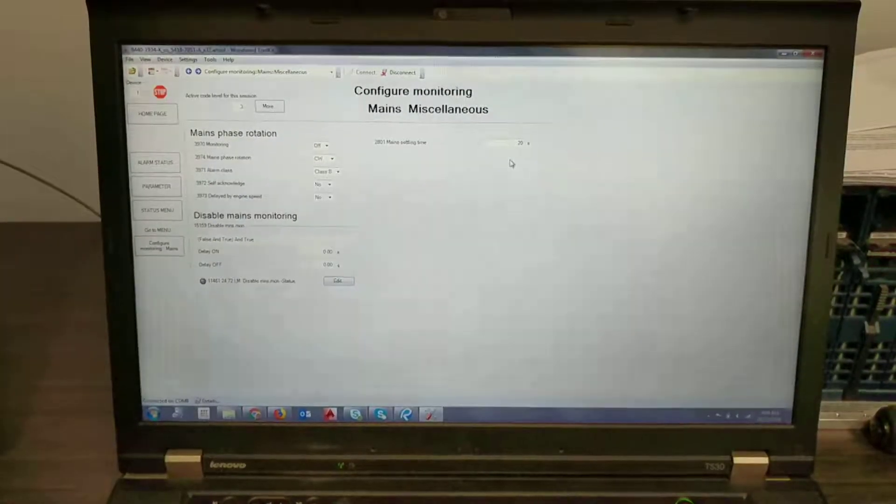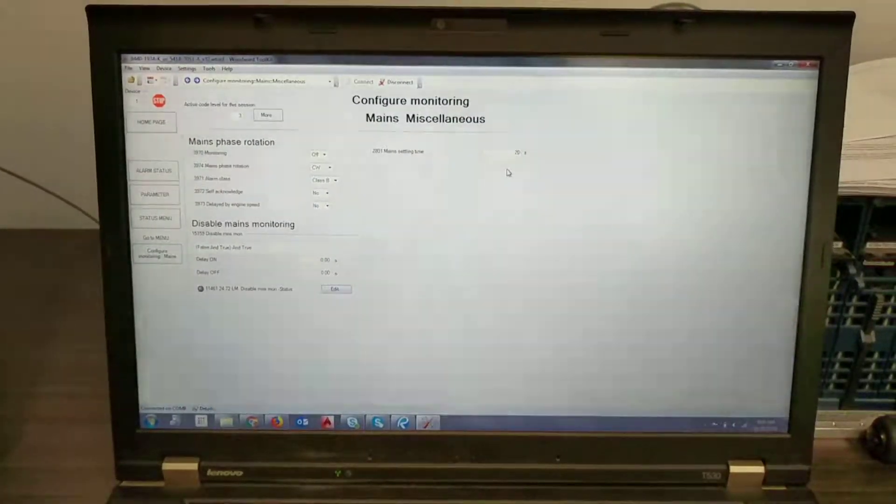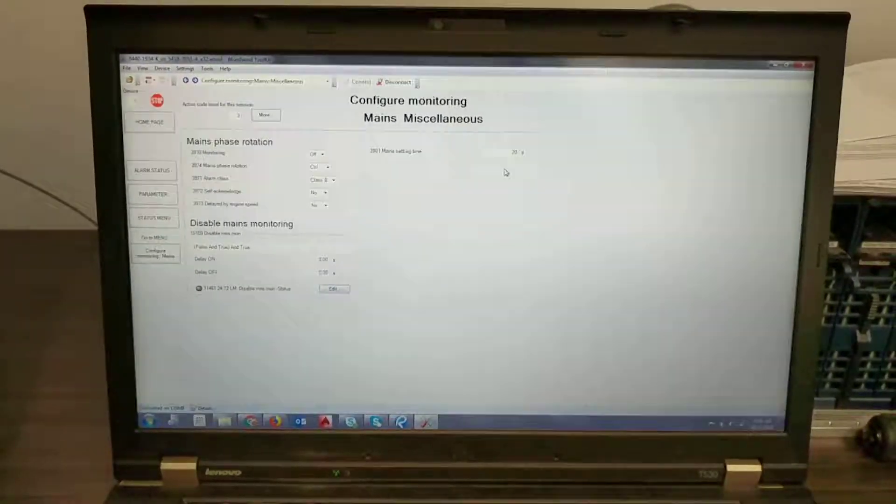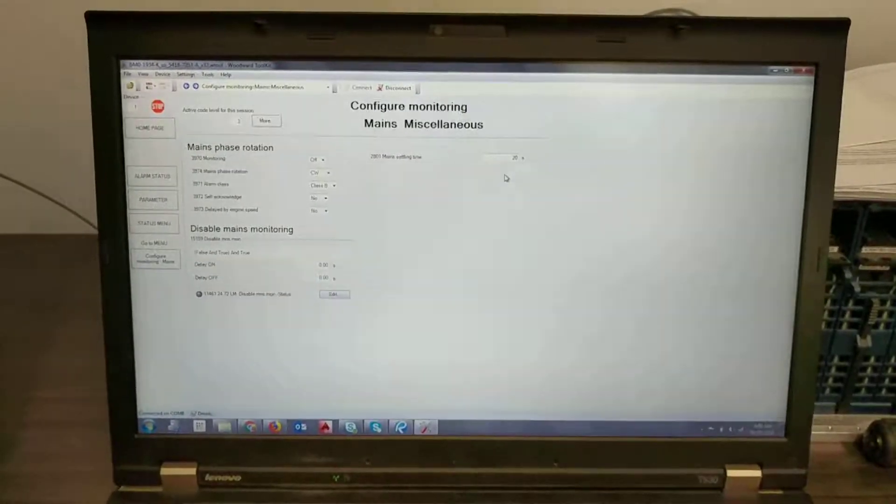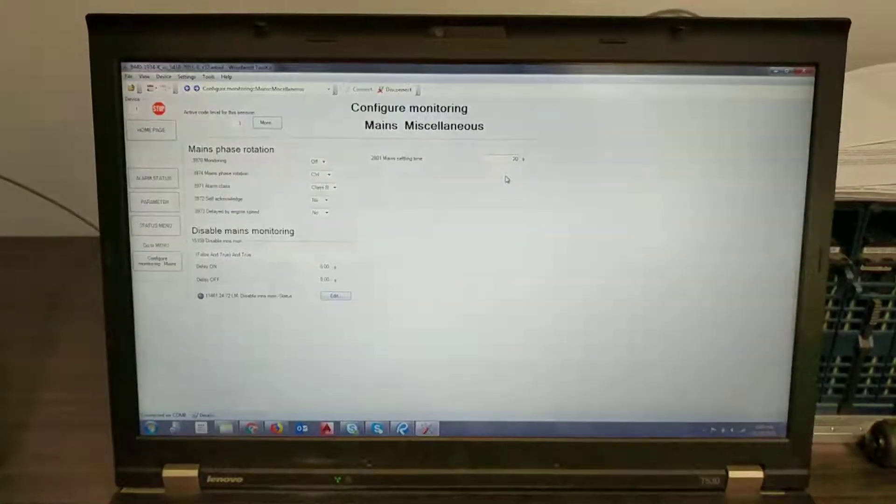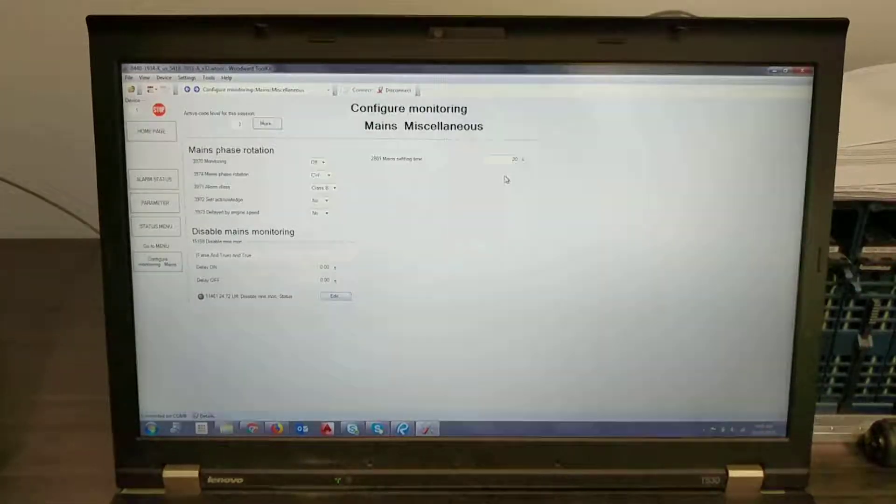So what that will do if you're using an auto mains fail feature, once you transfer to gen it will stay on generator. When the utility is healthy it needs to be healthy for five full minutes before it would transfer back to the utility. Now during that five minutes if the utility fails again, once it comes back it will have to count down that five minutes all over again. So thanks.